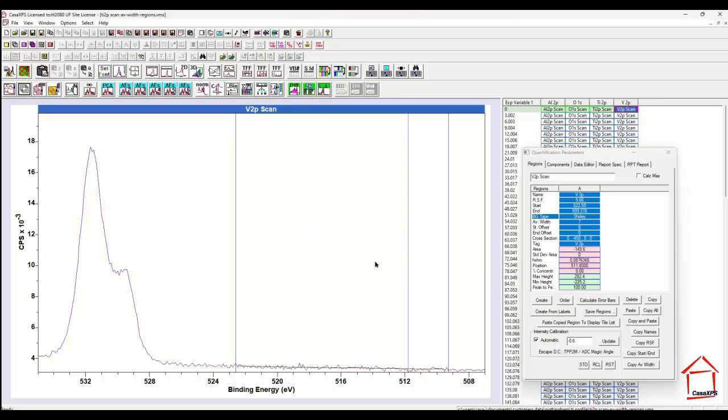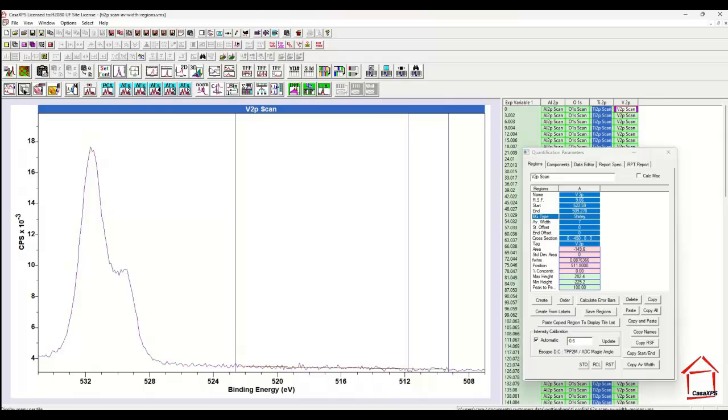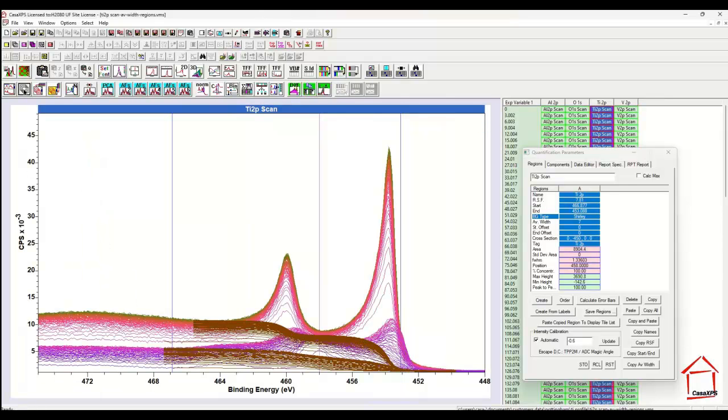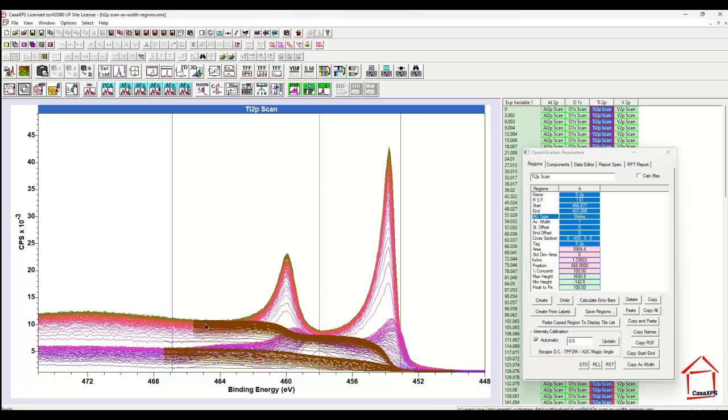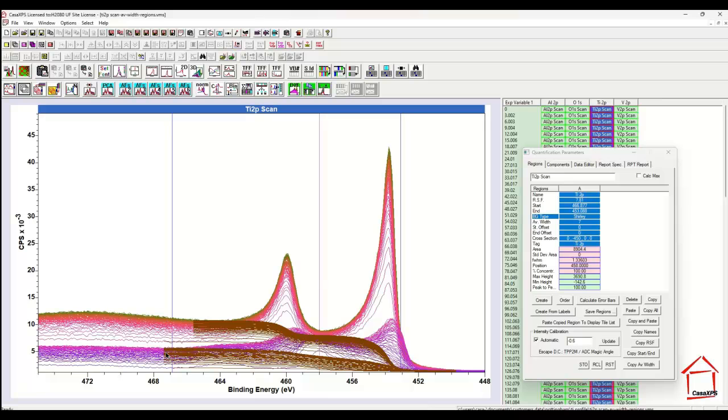So we need to make sure that we use an average width that is appropriate for each phase of this depth profile. If I look at the titanium data, for example, you'll see that the titanium starts off as an oxide and then as the profile continues the metallic form of the titanium appears and the background characteristics are slightly different. So here's an example where I might alter the average width and also the region itself depending on which of these sputter cycles I'm considering.